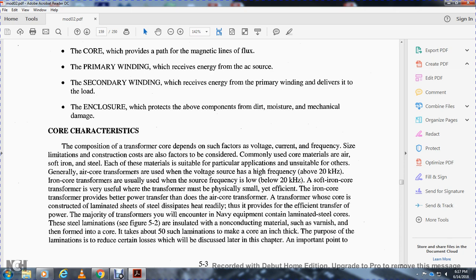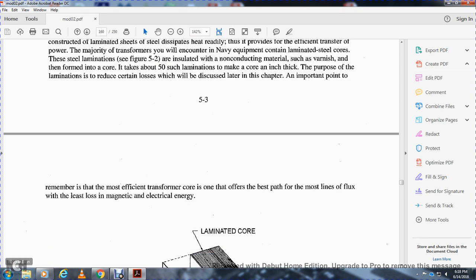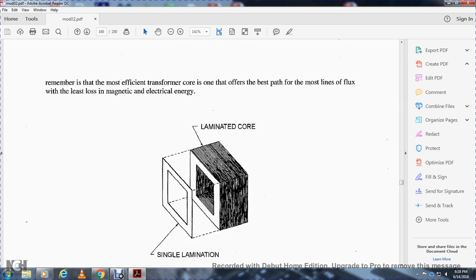The iron core transformer whose core is constructed with laminated sheet steel dissipates heat readily, providing an efficient transformer. The laminated steel cores are illustrated in figure 5.2. Steel laminations are insulated with a nonconducting material such as varnish, formed into a core. It takes about 50 such laminations to make a core one inch thick. The purpose of lamination is to reduce certain losses, discussed later. The most efficient transformer core is one that offers the best path for the most lines of flux with the least magnetic loss.